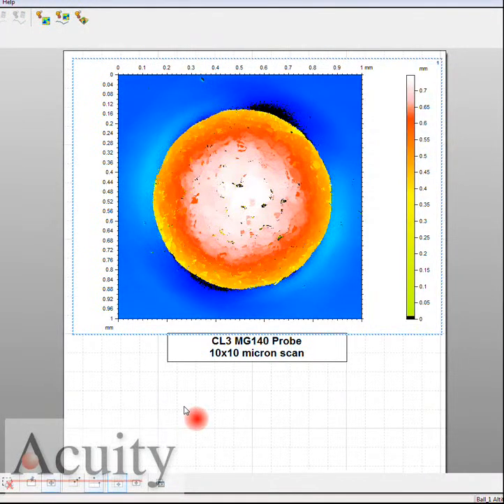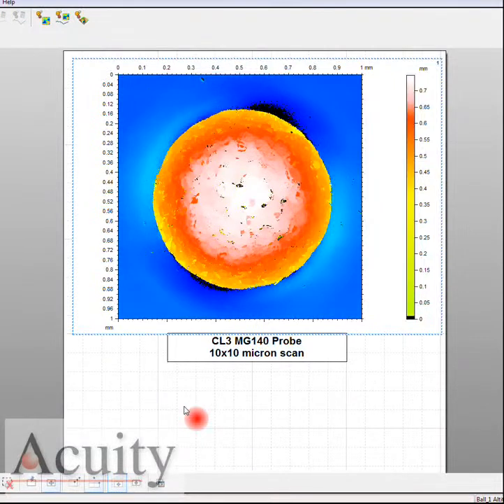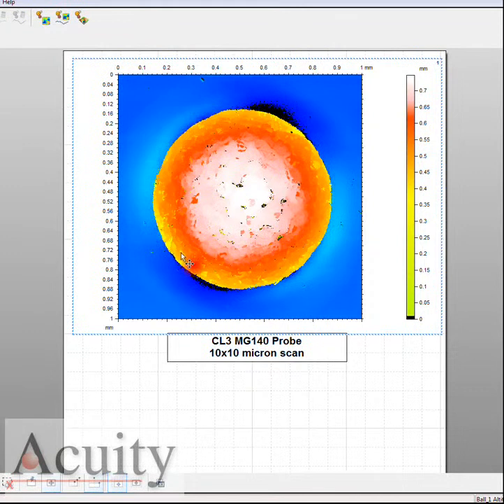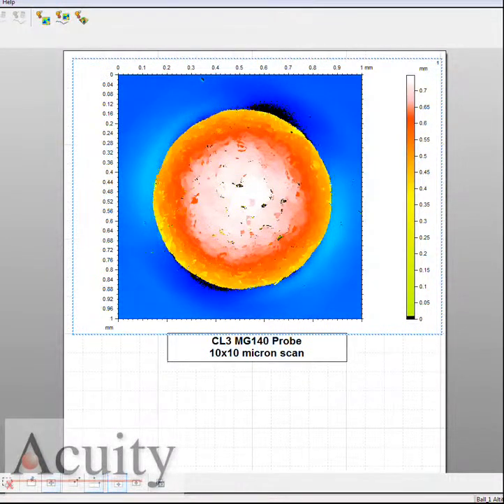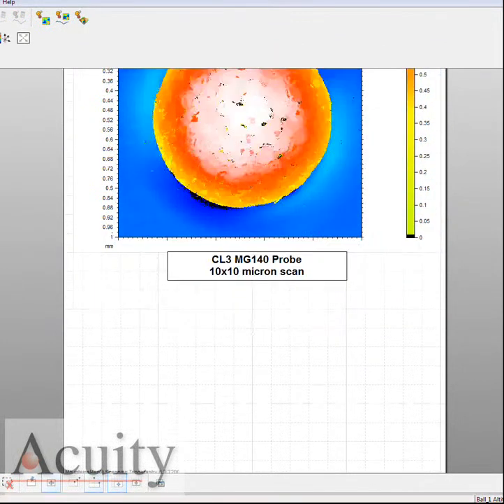In this application we're using the CL3MG140 probe, taking data at a density of 10 by 10 microns. Here you can see we're getting very good signal on this round circular target.